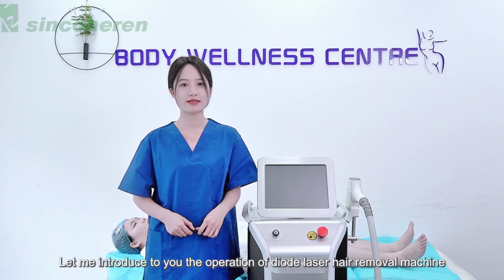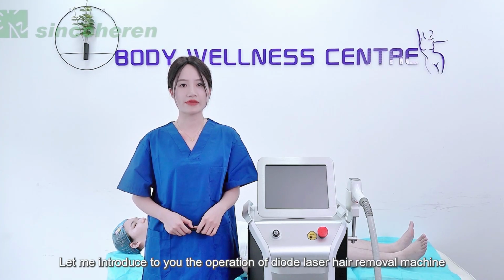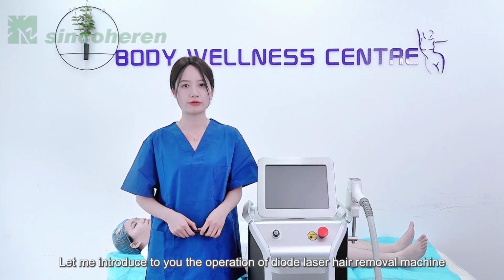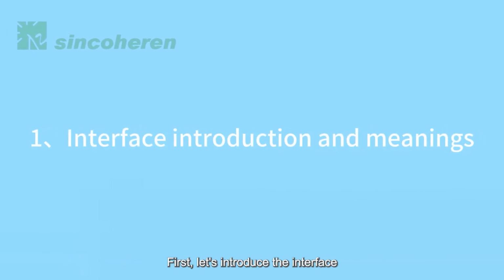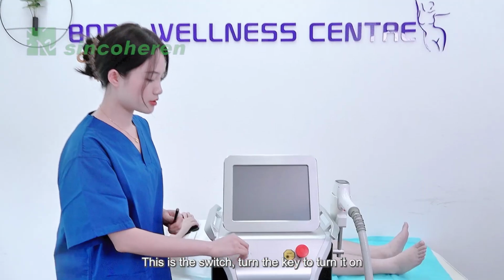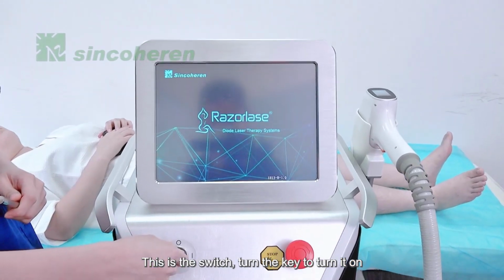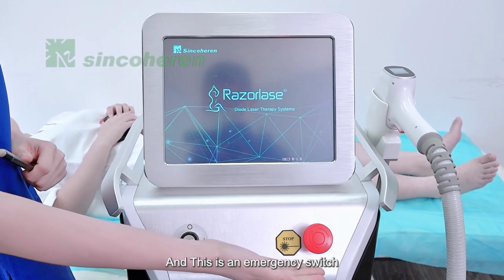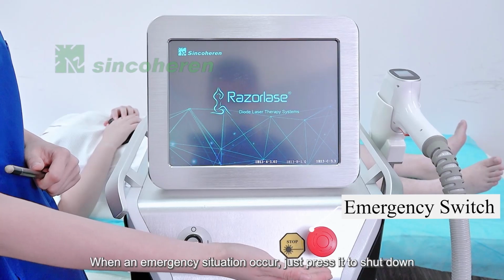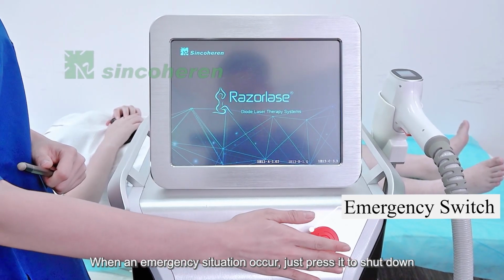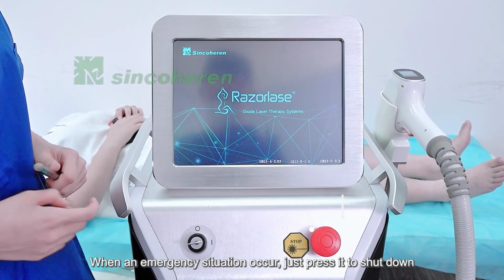Hello everyone. Let me introduce to you the operation of diode laser hair removal machine. First, let's introduce the interface. This is the switch, turn the key to turn it on. And this is an emergency switch. When an emergency situation occurs, just press it to shut down.